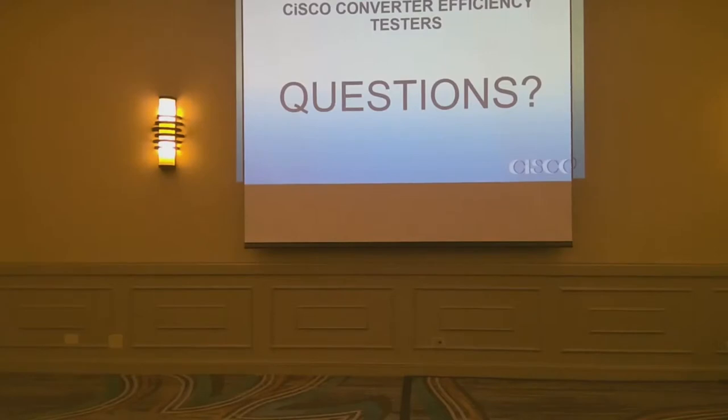Anyway, like I say, we have updated. You mentioned New Jersey requires doing that quarterly. Doesn't CFR require it annually, 75 or 60? I think our test fitters do it as part of RATA, but I don't know how they do it. Most test teams have to do a pre and a post efficiency test. Then they're allowed to correct their numbers by the efficiency number. Yeah, the testers do. I don't know of any CEMS regulations. I know California tried to push San Diego into doing it on a quarterly basis. They kind of resisted it. But it's written right in the 2005 manual in New Jersey, right?